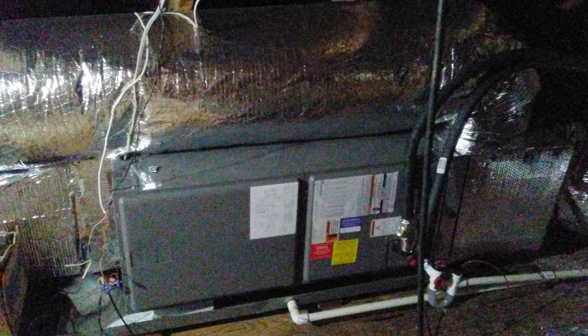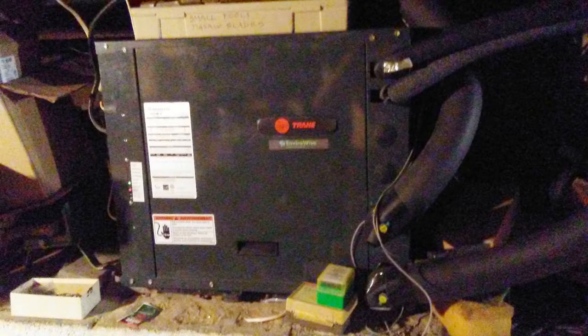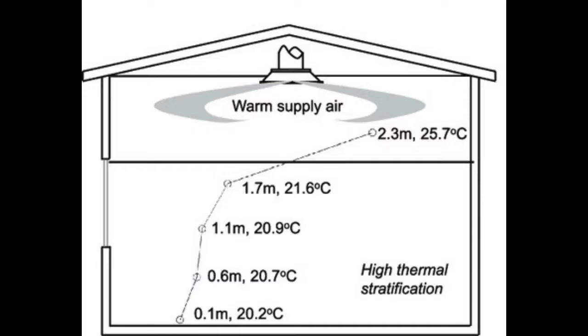But I've also got central air conditioning, also geothermal, and running off a separate heat pump. Why not just use that in reverse for heating? One reason is that the round diffusers in the ceiling were designed to disperse the cooled air horizontally along the ceiling and would all have to be replaced with square registers that direct the heated air downward. That would be expensive as well as disruptive.